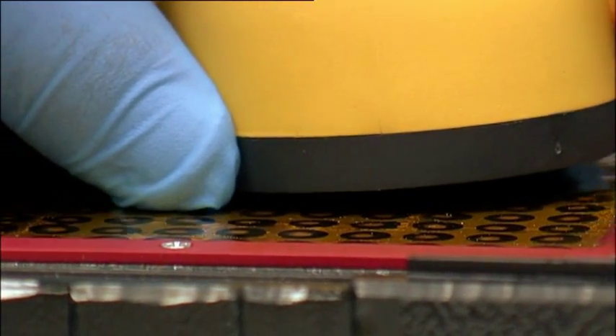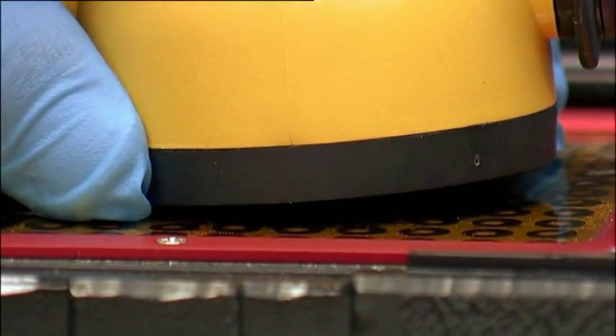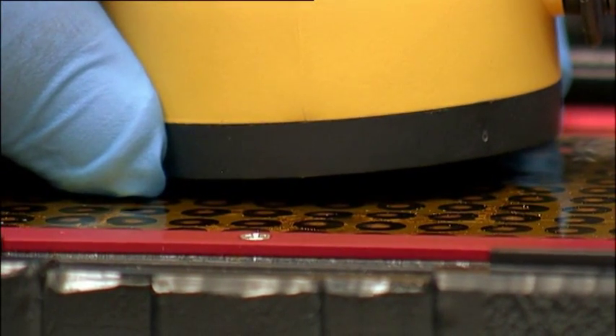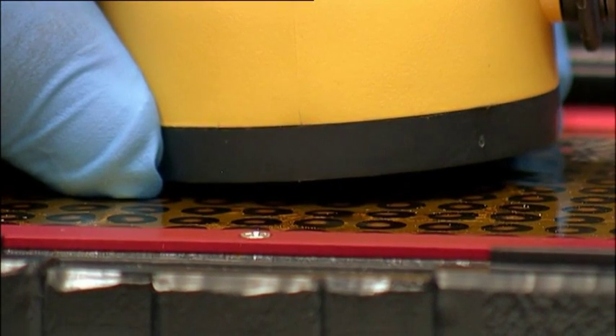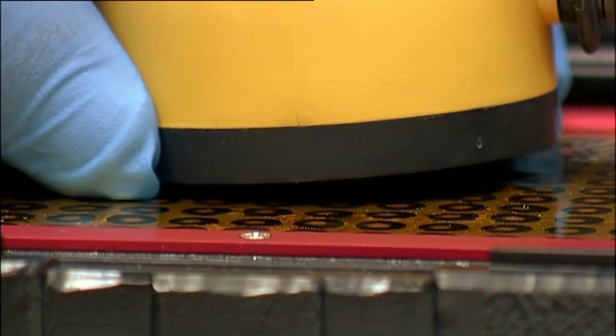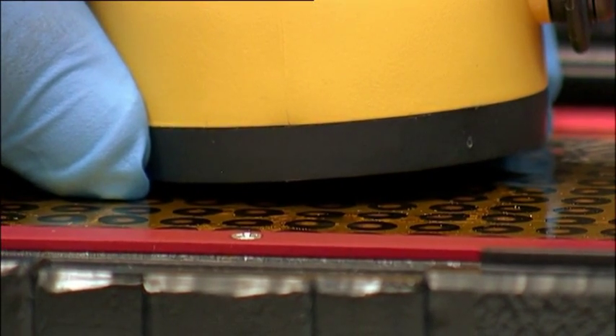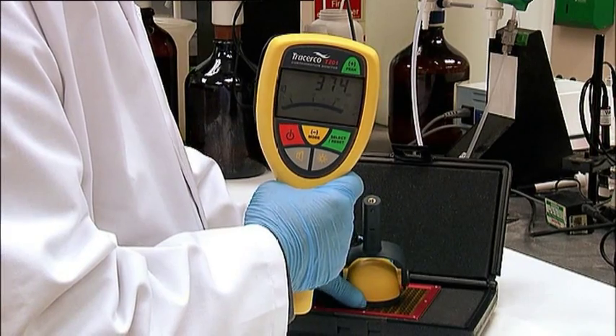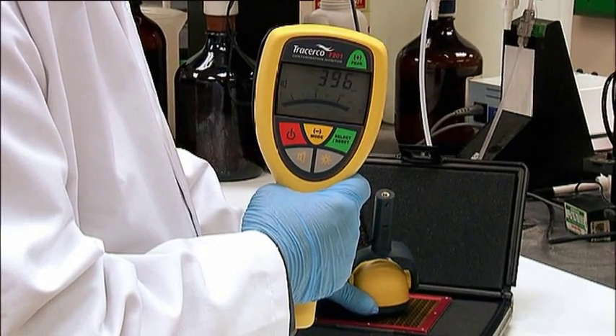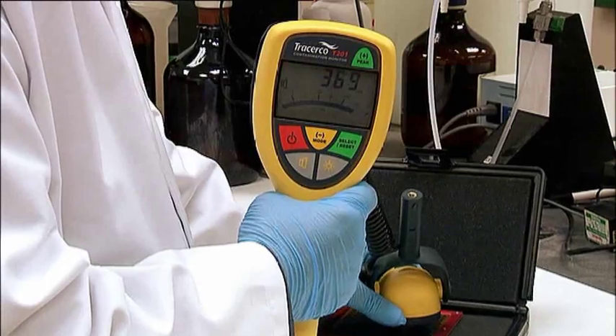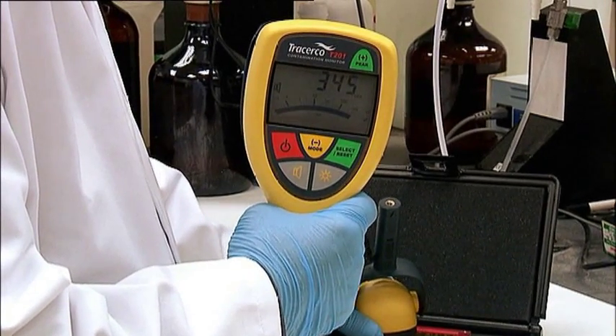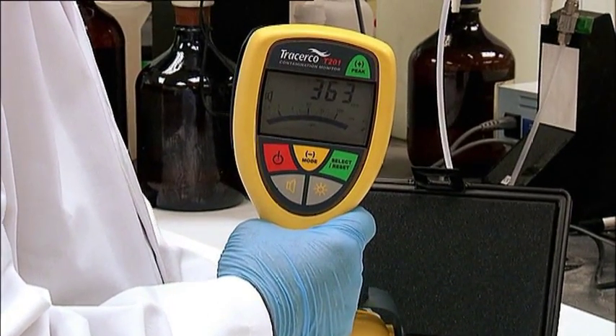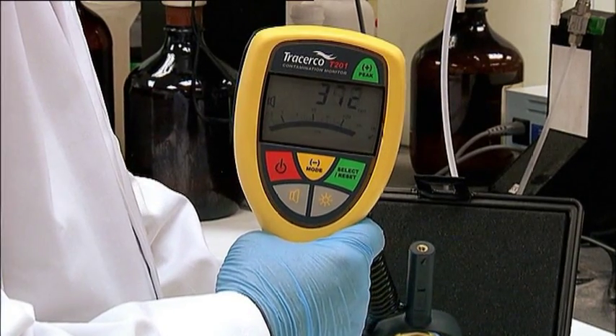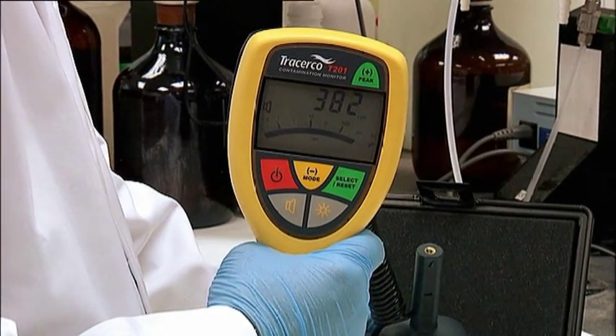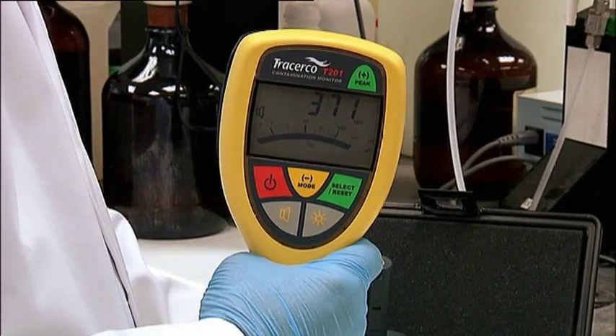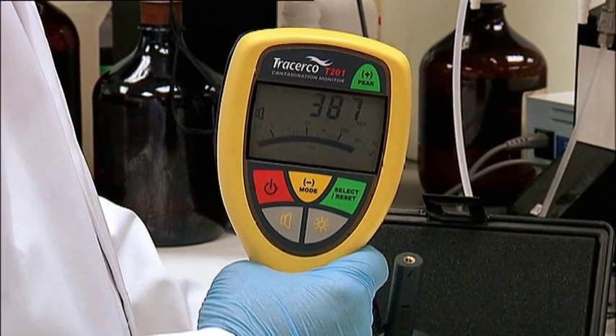The 3 mm distance has been selected to avoid contaminating the detector head through direct contact with the surface and to reduce the risk of puncturing the detector face with sharp objects. This distance has also been used to calibrate the response of the instrument. If the audible option is selected, the monitor will respond in accordance with the radiation level being detected. Since the sensitivity with which the probe detects radiation is greatly influenced by the distance from the source, the reading on the monitor will change as the probe is moved.